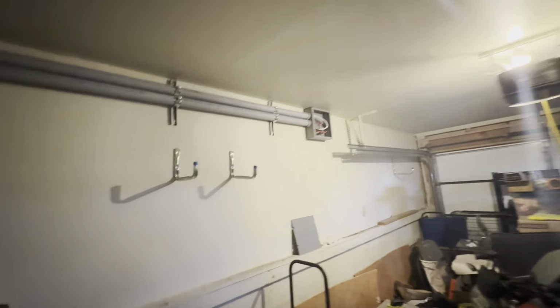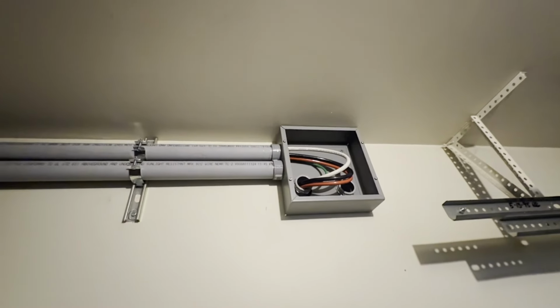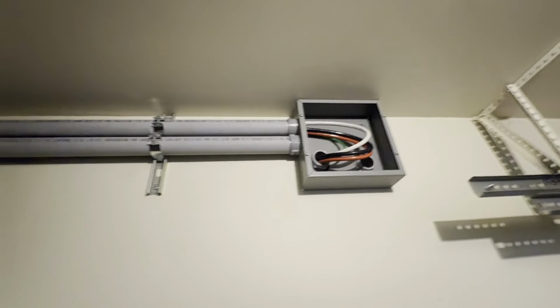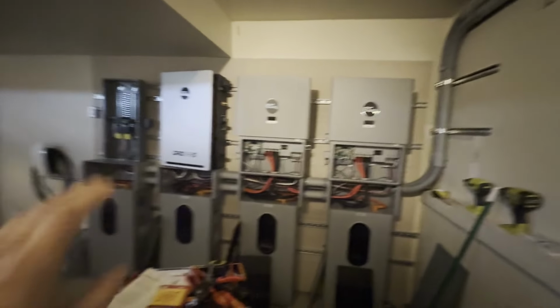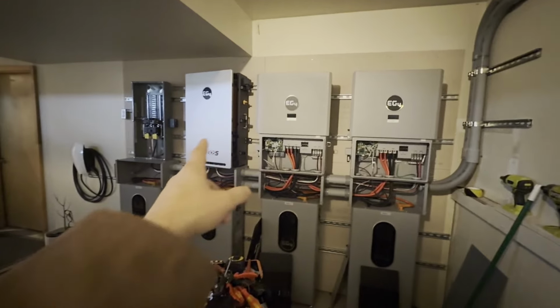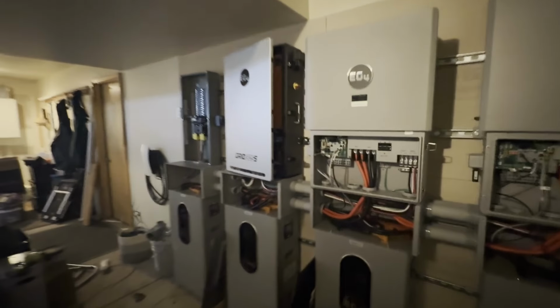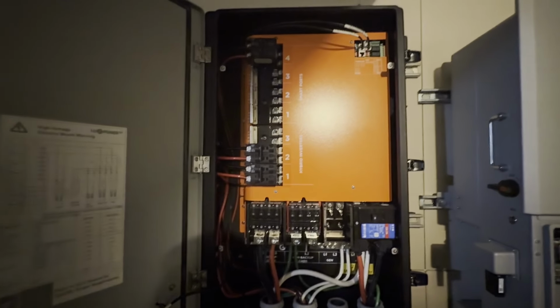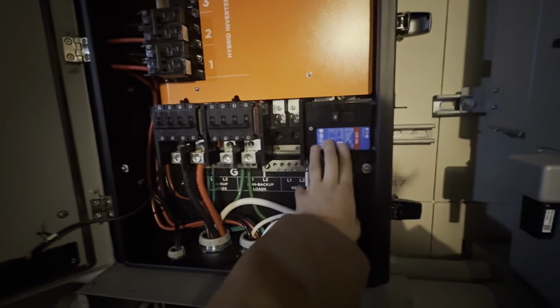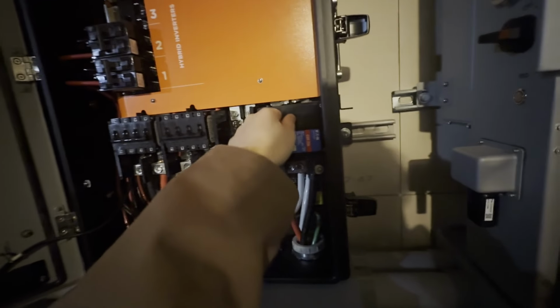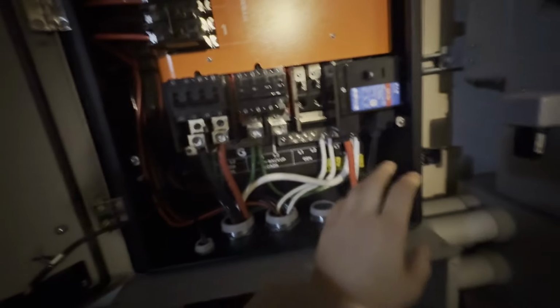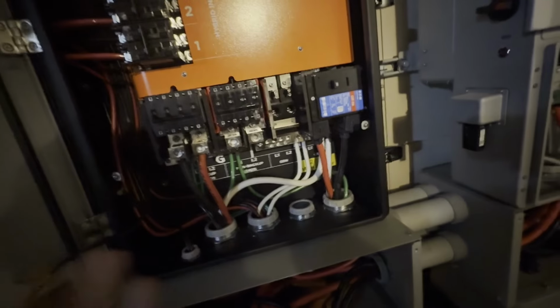It's got two-wire cables. So you've got hot, neutral, and then the ground. It goes through the top 2-inch PVC conduit there over to the Grid Boss. So that's the brains of the system. It's also called a microgrid interconnect device, or MID. In this case, this is an optional thing that you can do here, but I'm putting in a 200 amp breaker, otherwise you can just connect straight to it.